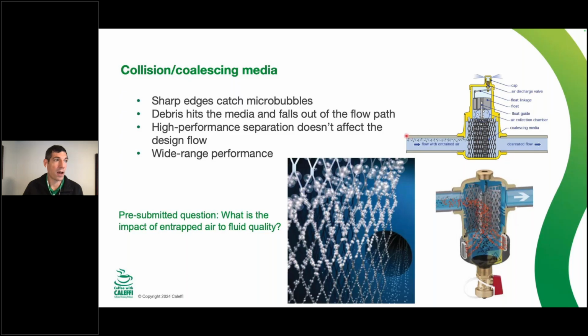So if we just had a T here with an air vent coming out the top, we're going to get a little bit of air. We're not going to get a lot of air out of that system, because the velocity is going to take that entrained air, the little micro bubbles, right past that separator and out to the system. So coalescing media is what makes a separator and not just an air vent. Also, the big bell of an air separator slows down that velocity so it's easier for the air to separate. So you can cut some cost out of these and make them really skinny, but they're not going to separate air as efficiently.